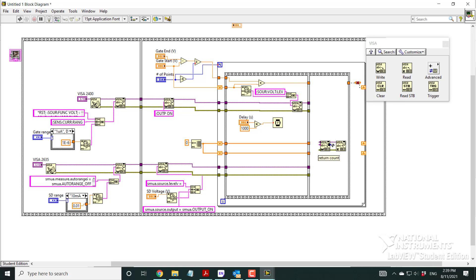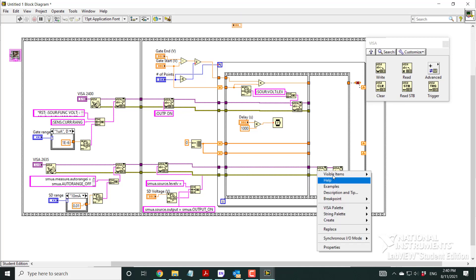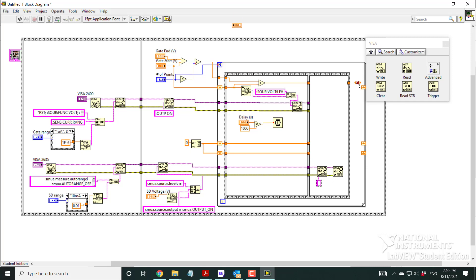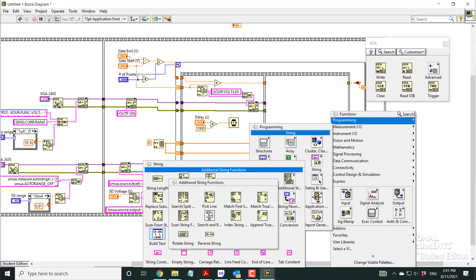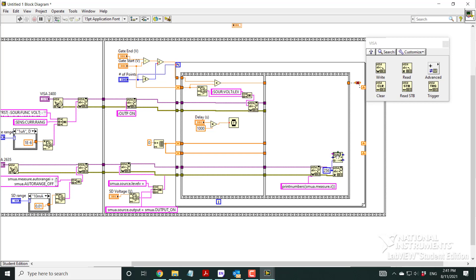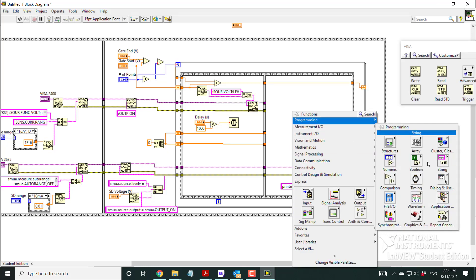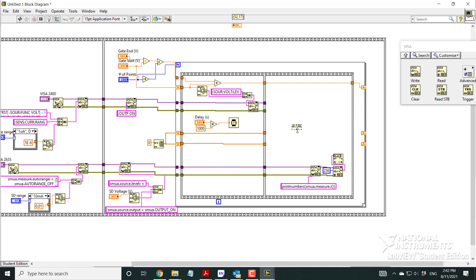In the next frame, I perform the SMU read from the 2635. I send the command 'print(smua.measure.i())' via VISA Write — this is the print number command we used earlier. Then I use VISA Read with a 256-byte buffer to receive the response from the instrument. The returned string is then converted from a string to a numeric value.